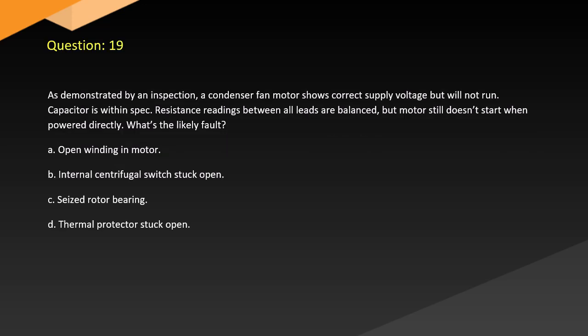Question 19. During an inspection, a condenser fan motor shows correct supply voltage but will not run. Capacitors are within spec. Resistance readings between all leads are balanced, but the motor still doesn't start when powered directly. What's the likely fault? A. Open winding in motor. B. Internal centrifugal switch stuck open. C. Seized rotor bearing. D. Thermal protector stuck open.